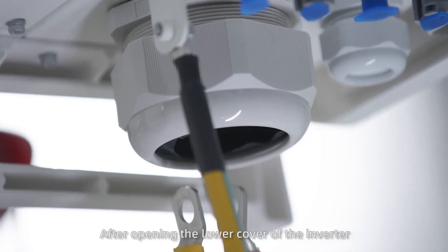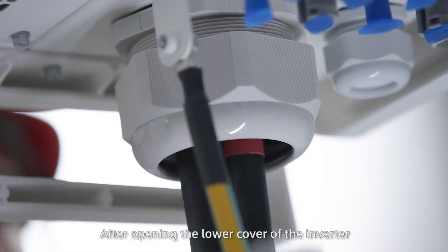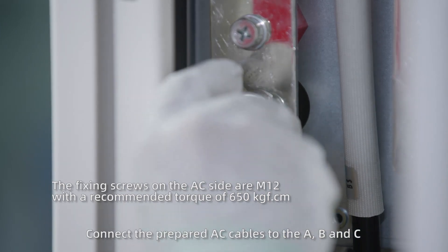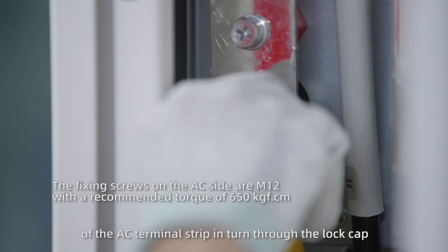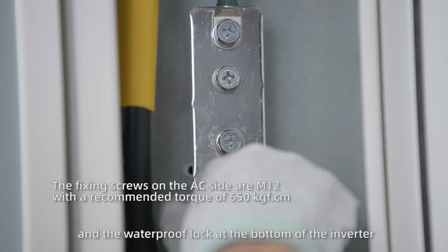After opening the lower cover of the inverter, connect the prepared AC cables to the A, B, and C of the AC terminal strip in turn through the lock cap and the waterproof lock at the bottom of the inverter. Next, tighten the lock cap, and the AC cable connection is finished.